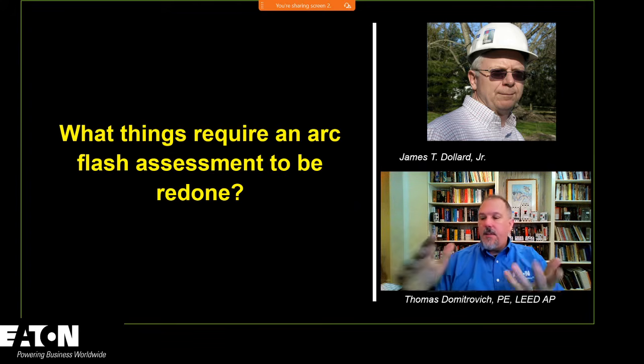So, what things require an arc flash risk assessment to be redone? There are two ways to do an arc flash risk assessment: we can do an incident energy analysis, or we can apply the arc flash PPE tables. Lack of maintenance, changing out a transformer, anything that would impact upstream available fault current, or anything that would impact the opening time of an overcurrent protective device, all of those things would trigger the engineer who performed that study to do it again.